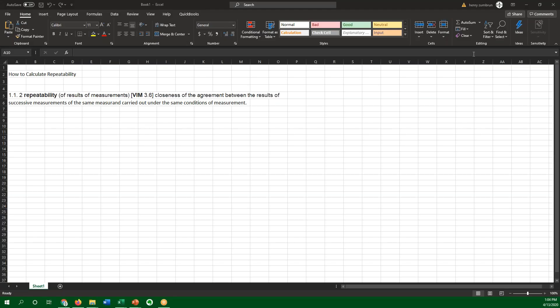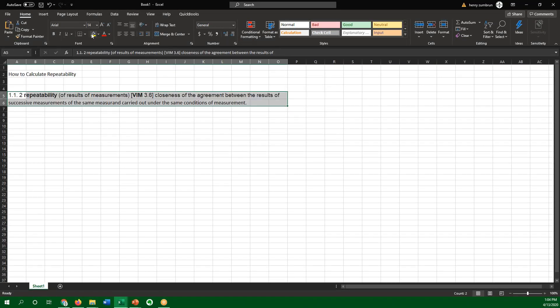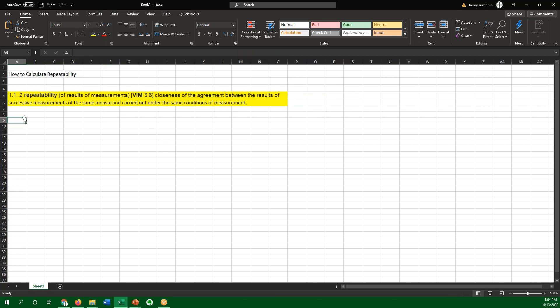Hi everyone. This is a real short video. I just wanted to show everybody how to calculate repeatability. If we look at what repeatability is per the VIM right here, this definition, repeatability of results, closeness of agreement between the results of successive measurements of the same measurand carried out under the same conditions of measurement.